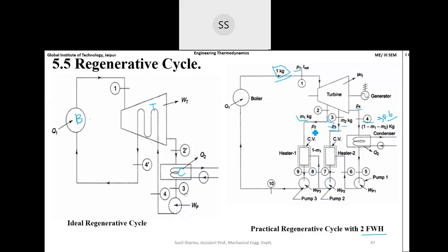So now here P2 pressure steam is already available, so again direct mixing takes place. After the direct mixing, this water and steam are again converted to very highly heated water of pressure P2. Now the weight is 1 kilogram, because this was initially 0.6 kilogram, then 0.8 kilogram after mixing here, and now this is 1 kilogram of water, at very high temperature.